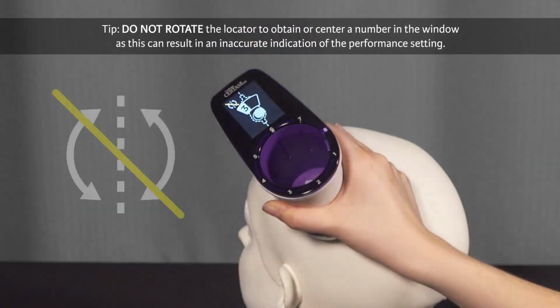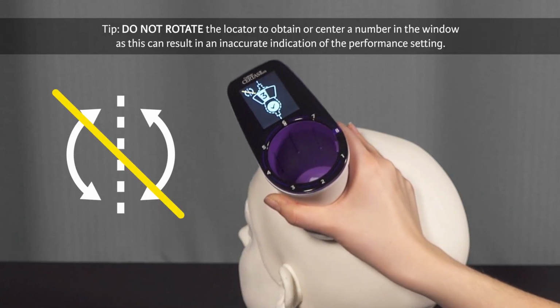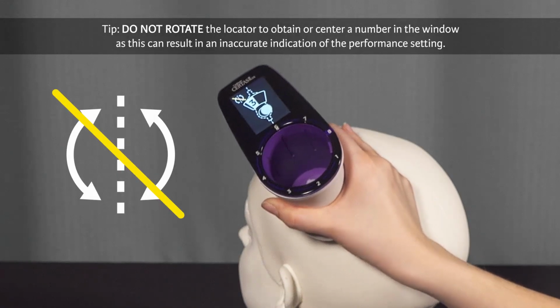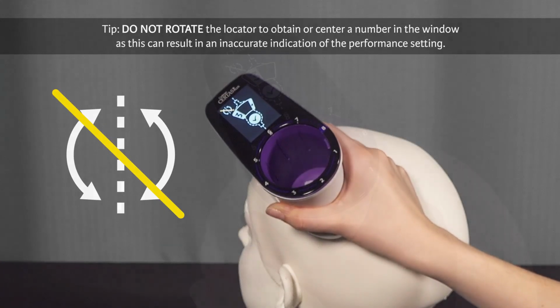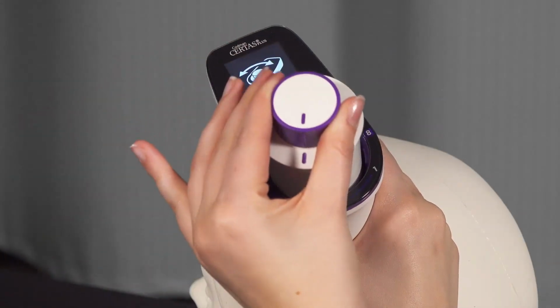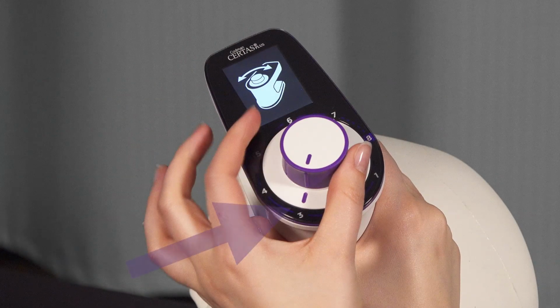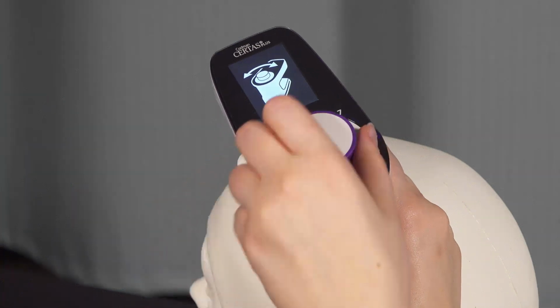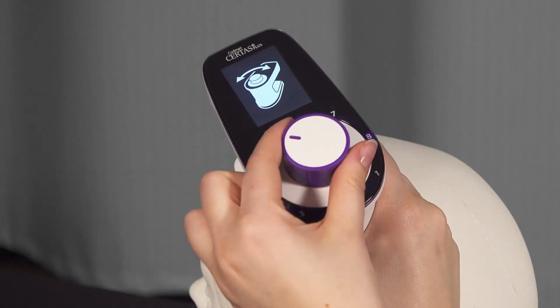Do not rotate the locator to obtain or center a number in the window, as this can result in inaccurate indication of the performance setting. Insert the adjustment tool into the locator so that the line on the adjustment tool is pointing towards the current performance setting. Turn the adjustment tool directly to the desired performance setting.